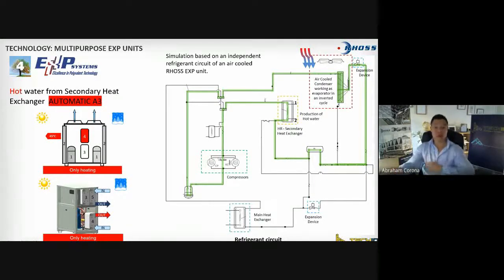So what the controller does is reverse the cycle of the refrigerant, and we have transformed the chiller into a heat pump in that circuit. As you see, now we are producing heat, 45, 55, in the secondary heat exchanger, and that goes now to the condenser that previously was working as a cool condenser. But now you see here on the top right, we have a second expansion device, and we are using that condenser as an air-cooled evaporator. So now the gases get expanded inside of this new evaporator. We are getting heat out of the environment into the refrigerant, we go into the compressor, and we complete the cycle. So now we are able to produce only heating.